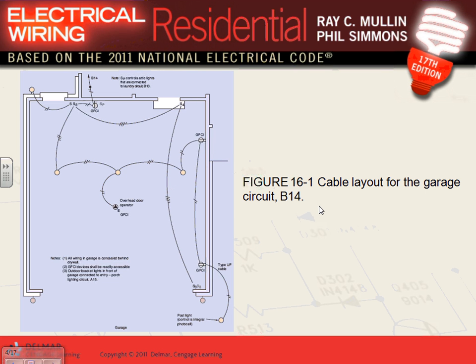Tao, my friend, why do you think we have 4 conductors here? Anybody can tell me, why do we have 4 conductors here? It's between a 3-way and 4-way switch. You have to have 2 travelers, right? And you need to have a neutral, because by code 2011 you have to have a neutral. What do you think the last one is? Switched hot. In this case, it's going to be switched hot. So 2 travelers, a neutral, and a switched hot. Any question as to how they did them?